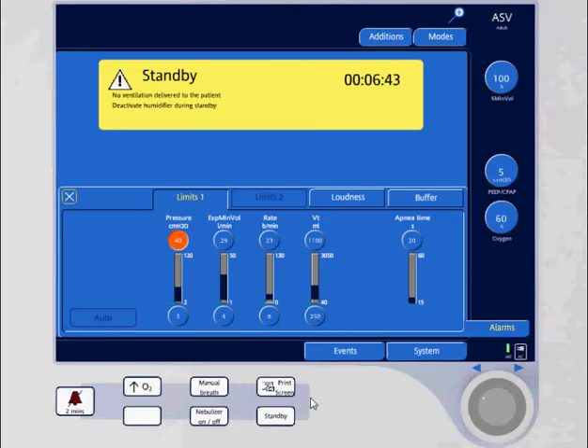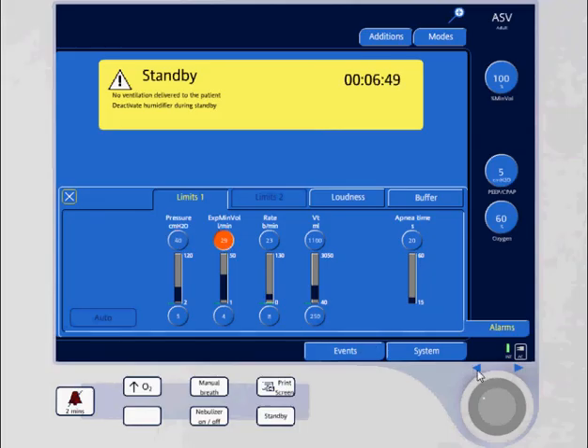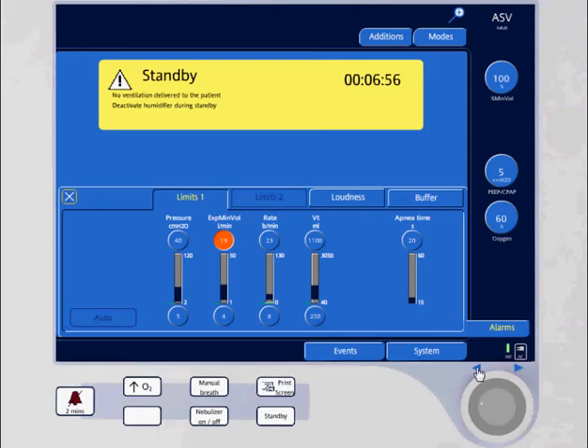I'm going through and selecting my limits for my high pressure limit. The high pressure limit is very important - it limits how high the peak pressure can titrate. In adaptive support ventilation, the pressure will only go up to 10 centimeters of water below my high pressure alarm setting.